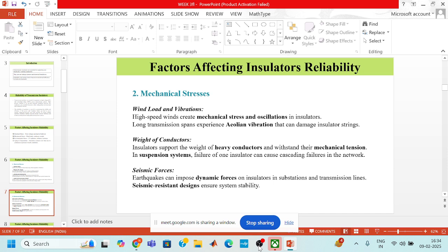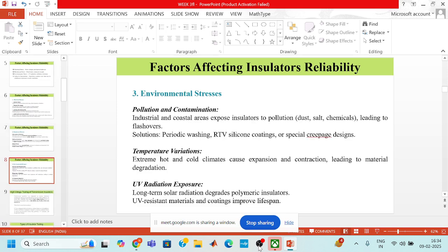Now, third is seismic forces. Earthquakes can impose dynamic forces on insulators in substations and transmission lines. Seismic resistant design ensures system stability. Now, the third factor is environmental stresses. Environmental stresses are due to pollution and contamination, temperature variations, and UV radiation exposure. In industrial or coastal areas, most insulators are exposed to pollution such as dust, salt, and chemicals, which can lead to flashovers.